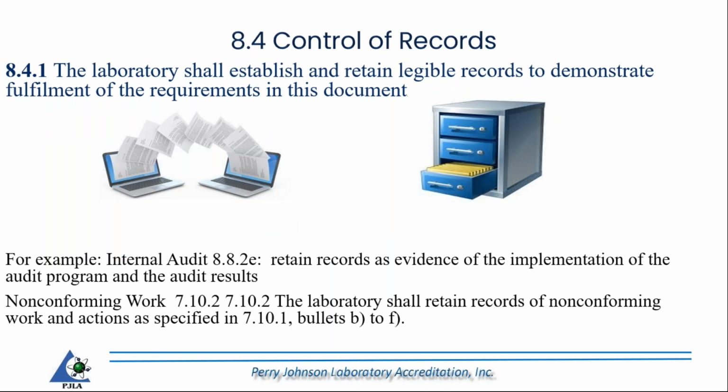8.4.1, the laboratory shall. Probably heard me say this before. That word shall is a requirement, should is a recommendation, may is a permission. So the laboratory shall establish and retain legible records to demonstrate fulfillment of the requirements of this document, this document being 17025. So of course your records that you maintain, you should be able to read them. If you are still maintaining hard copies, they should be protected, of course, outside of the elements, in a hard file cabinet.